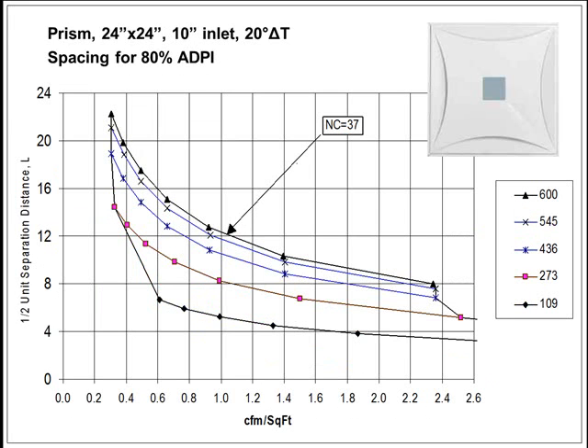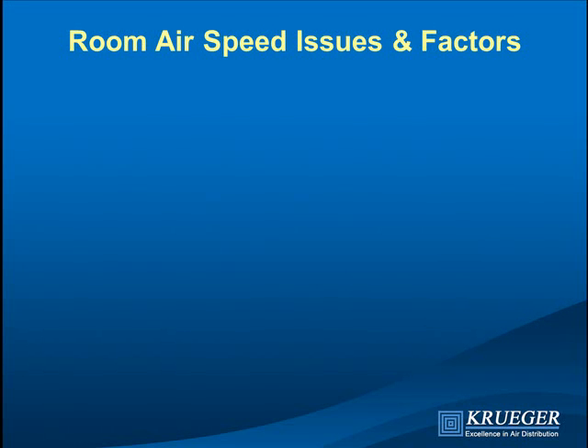We have other diffusers that fit the same backpan. The Prism is designed to replace the perf face in that same backpan. Running the same analysis, diffusers can be placed further apart and turned down to 0.4 CFM per square foot. Other diffusers will go down to 0.2 CFM per square foot. As for stuffiness complaints at low airflows — stuffy is a thermal comfort complaint meaning slightly warm, not an indoor air quality issue. A California research study found no problems running at 0.2 CFM per square foot in offices.